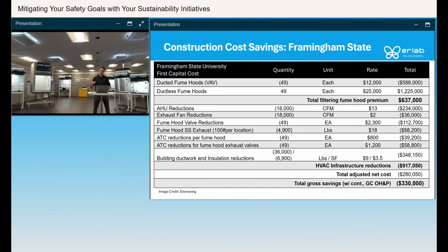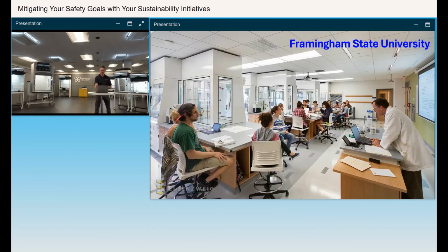So although the ductless fume hoods are about twice the cost of the ducted fume hood, that's because with the ductless fume hood, everything you need is included. You have the filters and fans right there. You don't need any infrastructure. By going with the 49 ductless fume hoods, they're able to reduce their air handling units by 18,000 CFM, which is a significant amount of money. And also, they'll be able to reduce their building ductwork by 36,000 pounds, saving almost $350,000. So overall, when you look at the premium of the ductless fume hoods versus the reduction of mechanical equipment they were able to get rid of because they weren't going with the 49 ducted fume hoods, they're able to save about $330,000 on the entire project and get the top floor of the building built.